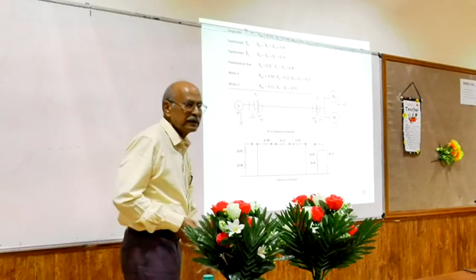So this is the negative sequence, you could catch the photo. Try to remember this structure; it's the same except the voltage source will not be there, that's all. For zero sequence, you have to be more careful. There is a transformer starred at the secondary side, so that has to be closed into delta, so if at all circulating current will be there, it would be indicated like that—same principle as before. So I can draw the zero sequence network also.